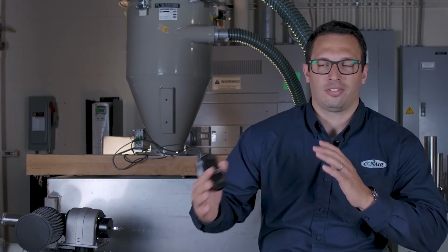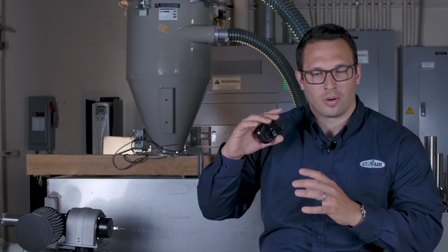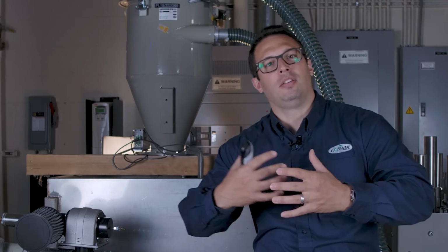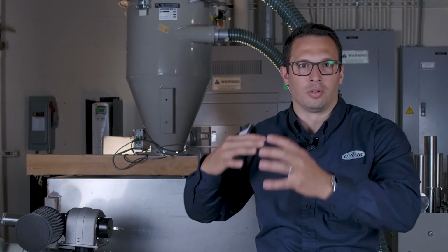But we also utilize analog inputs and outputs based on a variable sense. So if we have a variable speed pump like what we use for our wave conveying systems, or if we're modulating a wave valve where we're modulating the amount of air we're allowed to let into the pickup point, that's typically going to be on a 4 to 20 milliamp or a 0 to 10 volt signal. And that's something that we can vary.